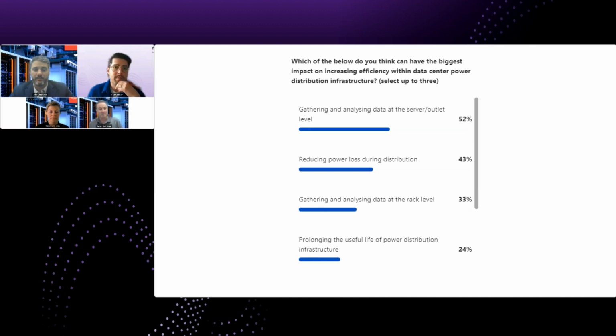What's interesting to me is the comment on distributing power at 400 and 415, which is really what the rest of the world typically does. But in North America, we bring in 480 and convert it all the way down to 120 volts. There's a lot of losses in those conversions, whereas if you distribute in the cabinet at 400 volts, you can use an auto transformer, and therefore you don't have the efficiency losses in the power conversion.